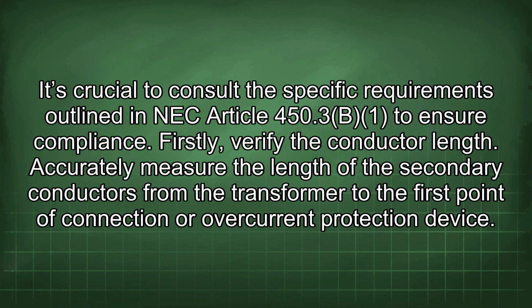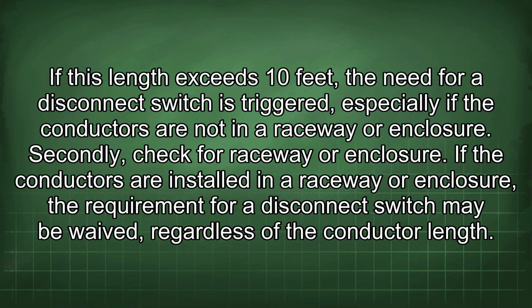Firstly, verify the conductor length. Accurately measure the length of the secondary conductors from the transformer to the first point of connection or overcurrent protection device. If this length exceeds 10 feet, the need for a disconnect switch is triggered, especially if the conductors are not in a raceway or enclosure. Secondly, check for raceway or enclosure.